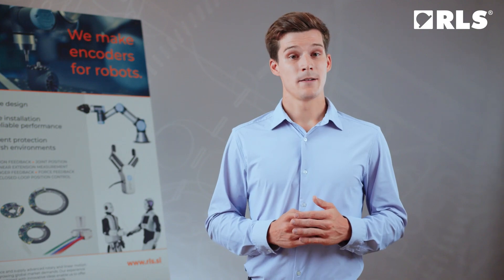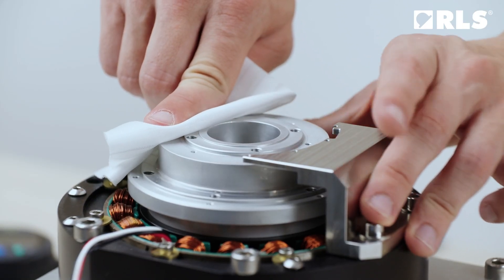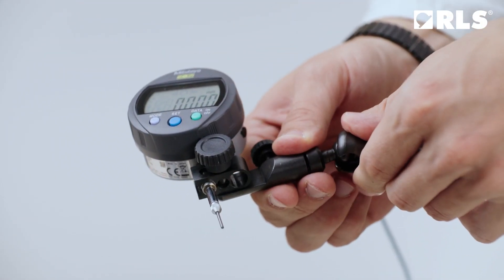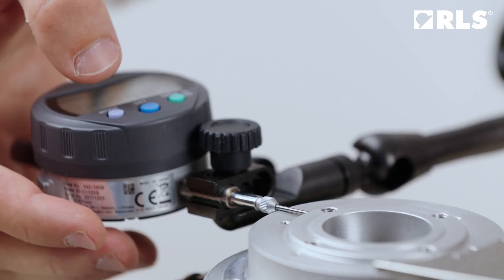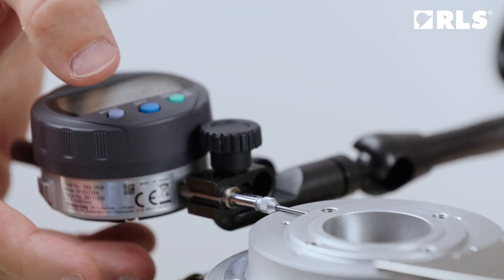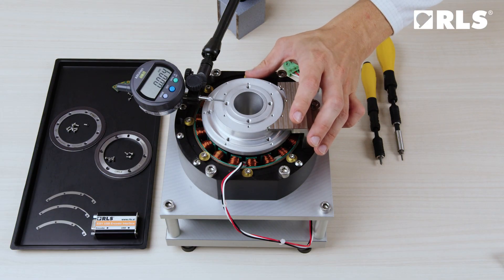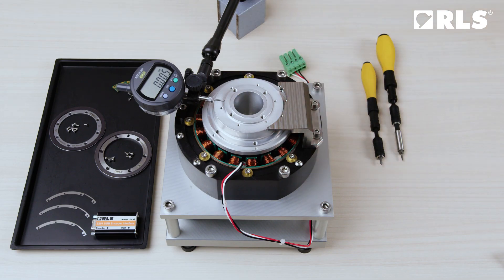Start with mounting the ring. First, clean the base from dirt and dust. Then check the eccentricity of the mounting shaft with the dial indicator. If runout is noticeable and running the AksIM self-calibration function is not possible, it is recommended to adjust the assembly, otherwise the accuracy of the system may be affected.